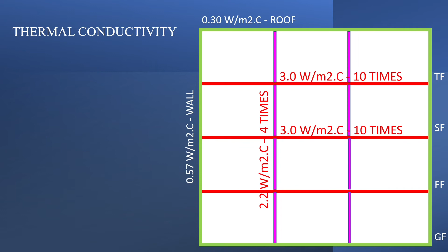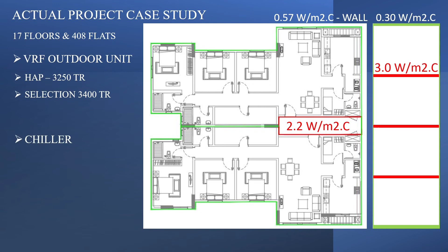The building has 17 floors and 408 apartments. Heat load was accurately calculated using HAP software. The total VRF outdoor unit capacity for the complete building, considering all partitions, was 3250 TR based on HAP calculation. When the supplier selects the outdoor unit, the capacity is increased to 3400 TR as the supplier does not have the same capacity outdoor unit based on actual requirements. When all the partitions were removed, the total chiller capacity of the same building was 1800 TR based on HAP calculation.